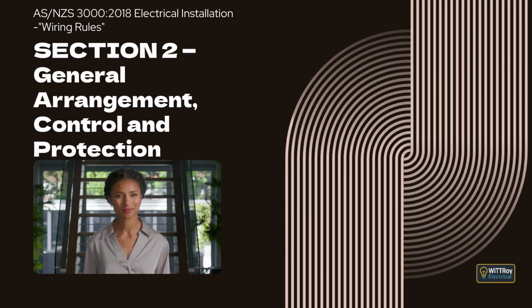Clause 2.5.3.1 Coordination between conductors and protective devices. This clause explains how the overload protective device must match the cable it is protecting. For the protection to work properly, two simple conditions must be met. The first condition is that the current the circuit is designed for must not be greater than the continuous current carrying capacity of the conductor.